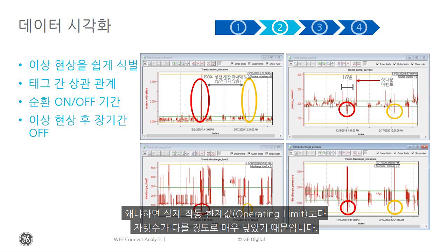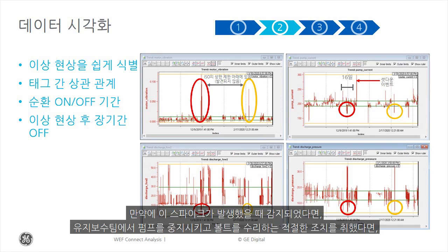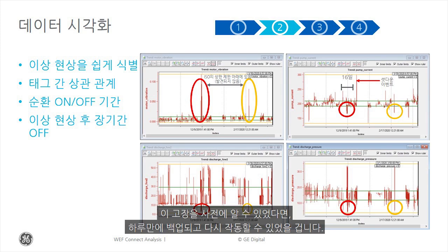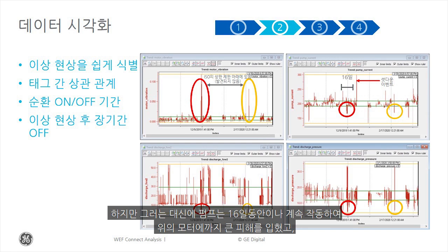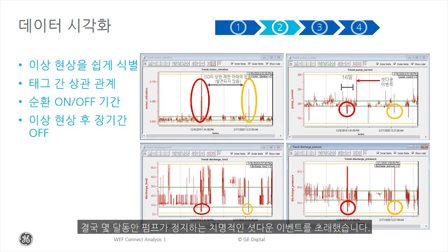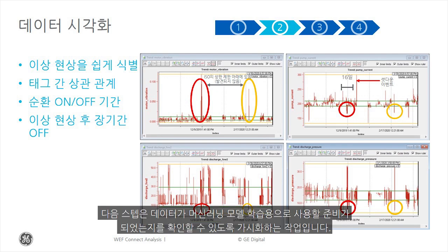the operating limit. Now, if it were detected when it had occurred, and if the team had taken proper action to stop the pump and simply repair the bolt, had they known about it, they would have been back up and running within a day. Instead, the pump continued to run for 16 days, wreaking havoc on the motor above, ultimately causing that catastrophic shutdown event that took the pump offline for months.